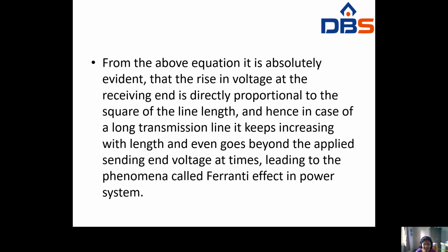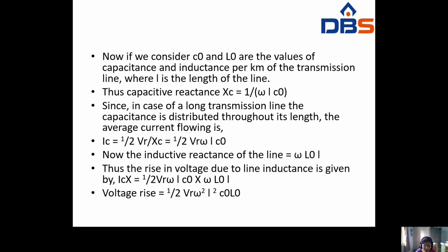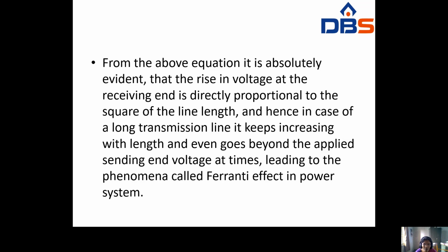So from this equation it is evident that the rise in voltage at the receiving end is directly proportional to the square of the line length. See here, the voltage rise is proportional to the square of the length of the line.